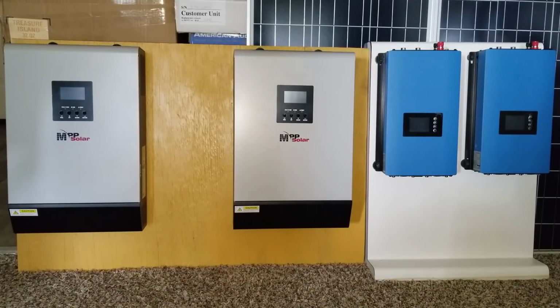They study the frequency, the hertz, back and forth, and see if the voltage is stable. If it has any fluctuation, then they sync. They don't just turn on right away and start throwing power. No, it thinks for a while. It studies the grid, the voltage, the watts, the hertz, the frequency, before it connects and starts producing power.